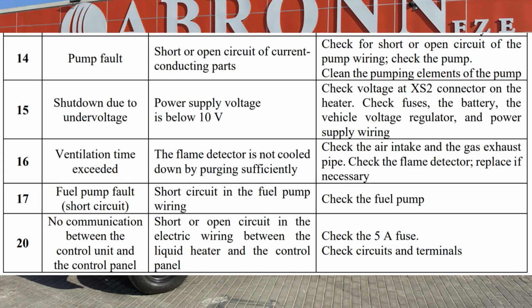www.autoterm.com. Warning. When starting the heater for the first time after installation, it is preferable to fill the main fuel line up to the input nozzle of the heater using a priming device. If there is no priming device, start the heater several times until the main fuel line is filled.